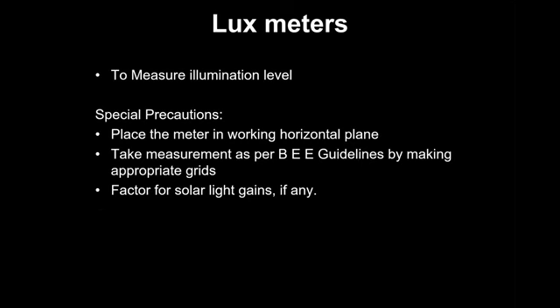So basically, a lux meter is used for measuring the illumination level. It's mostly a neglected part of the audit, because I have seen that in India we are comfortable at a lower illumination level than what is required as per the standard. I have yet to come across any industry where the illumination level is higher than what is required. So illumination measurement, lux measurement, is a notional thing. Most of the places we end up saying okay, you put in more lights if you want. Otherwise, as you are comfortable, please continue with the present system.